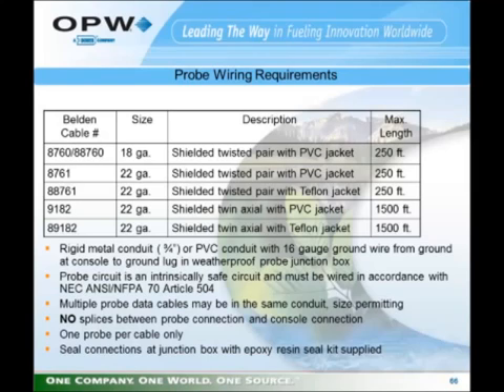If not using the Belden cables, it is best to check with tech support to see if the cable that you would like to use is a compatible electrical characteristic cable. All probe cables must be installed in rigid metal conduit, or they may be installed in PVC conduit if a separate ground wire is installed in that PVC conduit from the ground at the console to a ground lug in a probe junction box. Probe circuit is intrinsically safe and must be wired in accordance with NEC and NFPA rules. Multiple probe cables can be in the same conduit, size permitting. There are no splices allowed.